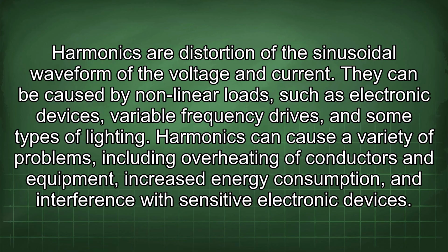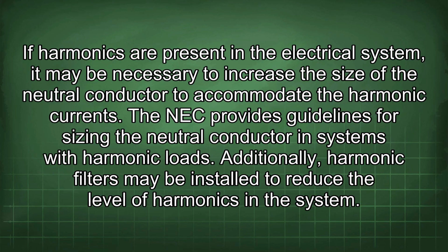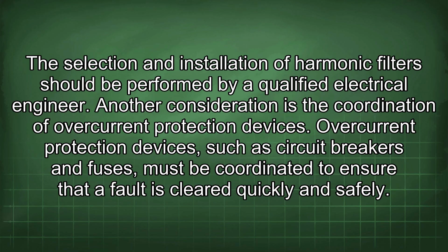If harmonics are present in the electrical system, it may be necessary to increase the size of the neutral conductor to accommodate the harmonic currents. The NEC provides guidelines for sizing the neutral conductor in systems with harmonic loads. Additionally, harmonic filters may be installed to reduce the level of harmonics in the system. The selection and installation of harmonic filters should be performed by a qualified electrical engineer.